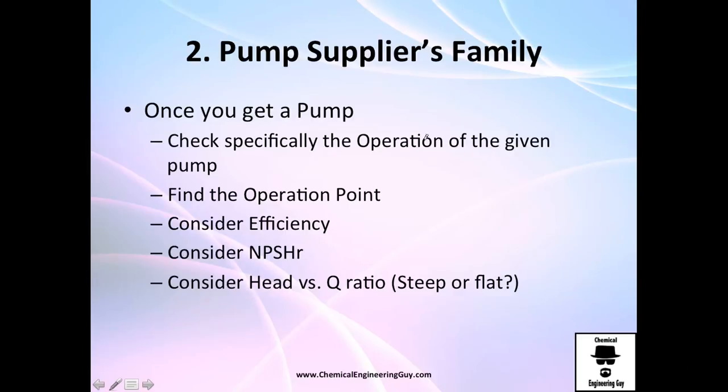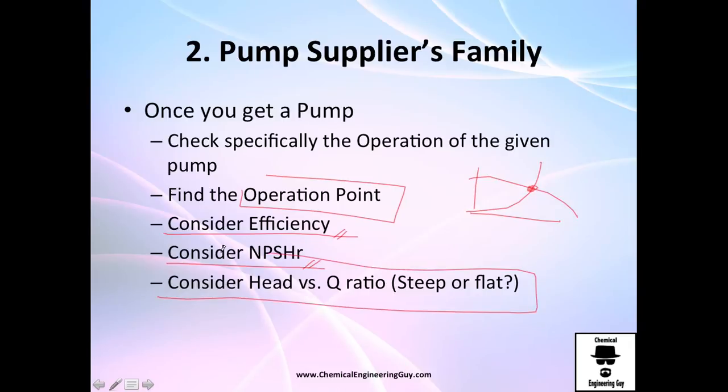Once you get the pump, we need to check for the specific point of operation. We find the operation point by crossing the system requirements versus the pumps we have. We then consider efficiency, consider NPSH-required requirements, and determine whether you want a pump which is very steep or very flat.